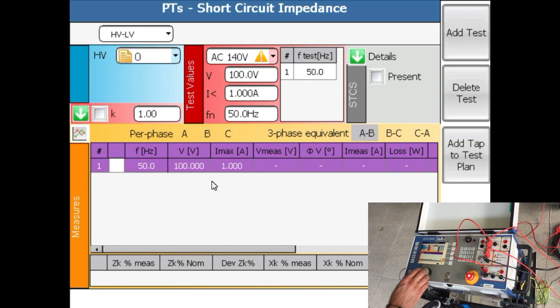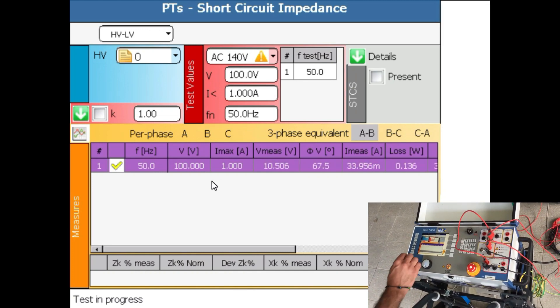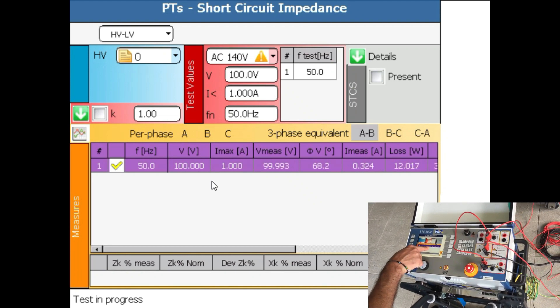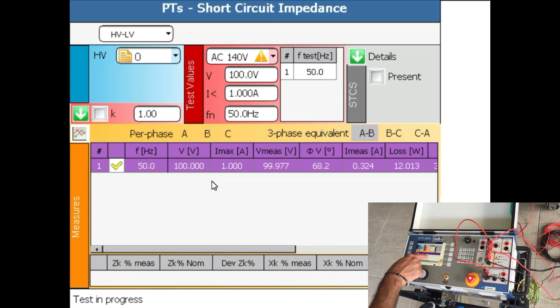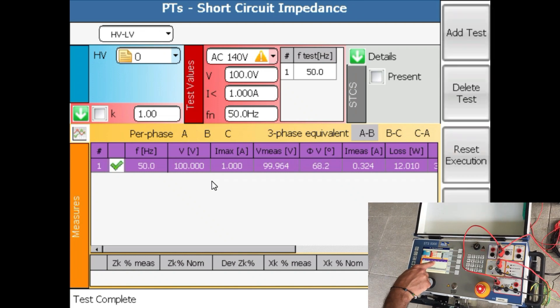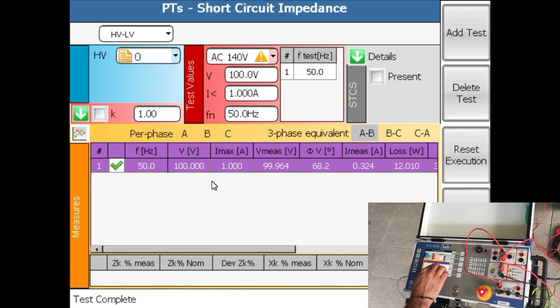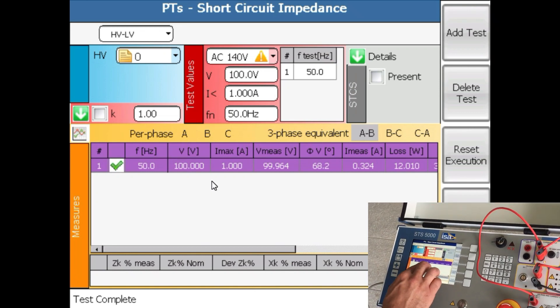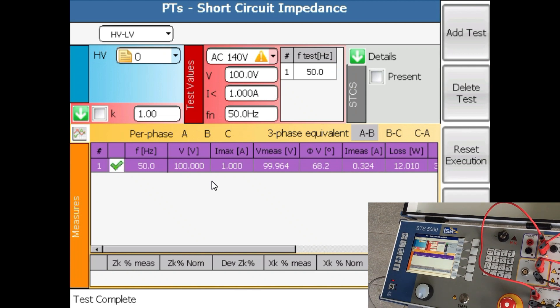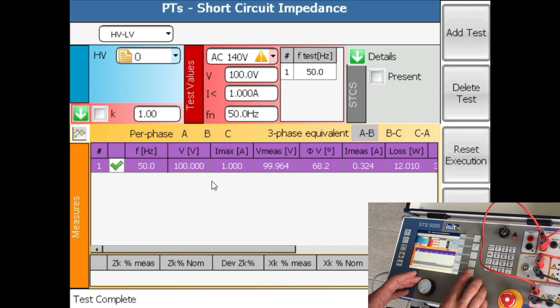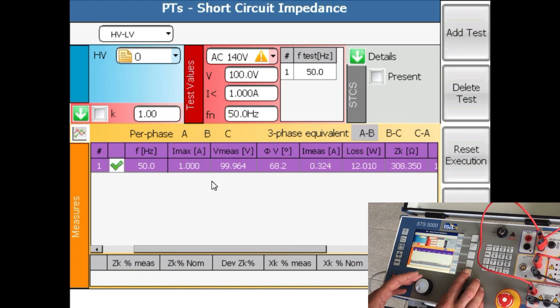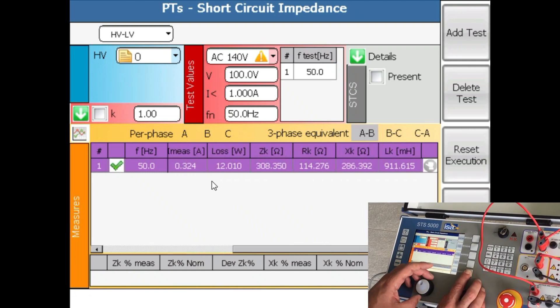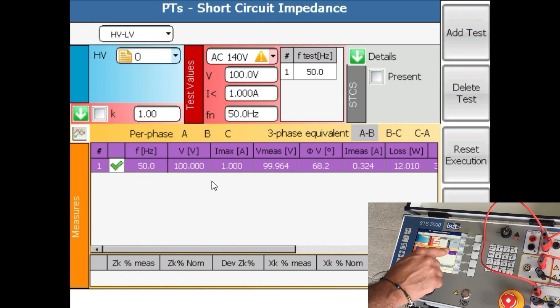What we are seeing here is that the voltage is 100.00 or 99.98 so it needs to stabilize. We generated for phases AB 99.964 very close to 100 volts. 0.324 amps are measured. We can also see that the losses are 12 watts. There is impedance, there is resistance, there is reactance and these are the data we got for these two phases.